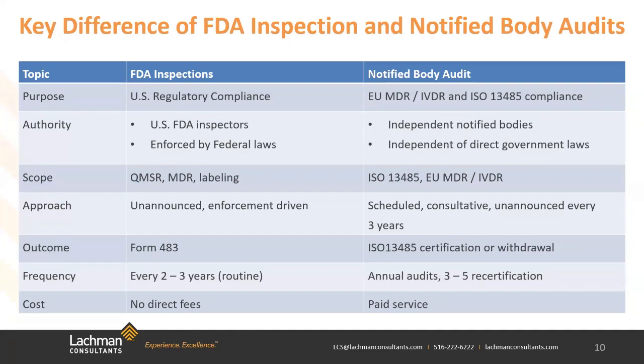The overall approach: FDA inspections are typically unannounced in the US. However, for international inspections, FDA typically does schedule these. And these inspections are for routine surveillance, pre-approval, or for-cause inspections, with investigators reviewing the design controls, CAPA processes, production records, complaint handling, and adverse reporting, and are heavily enforcement driven, whereas the notified body audit is generally scheduled in advance and you are given an audit plan to understand what they're going to be looking at, and is conducted in a consultative manner, but includes detailed reviews of the quality management system implementation, the risk management, and product compliance for surveillance and recertification audits.